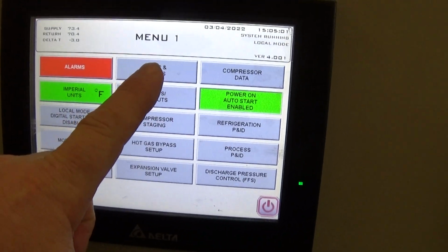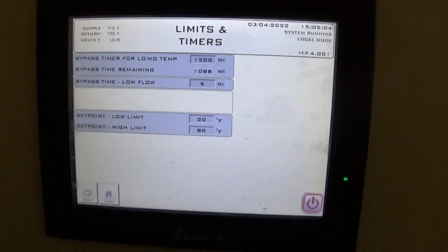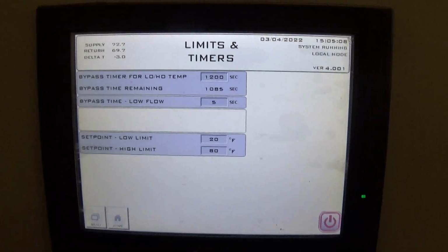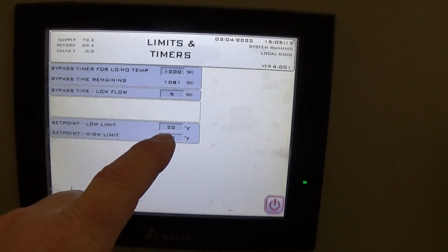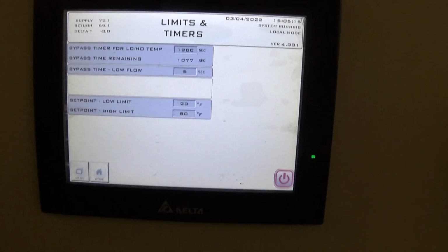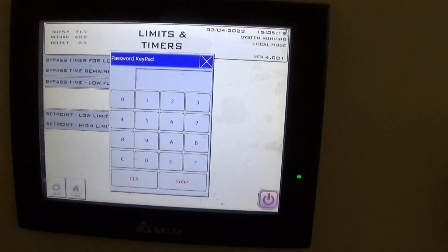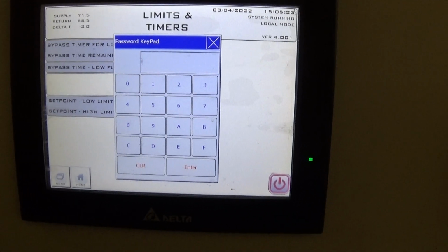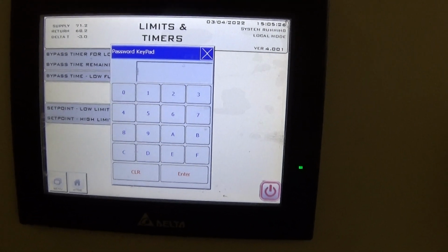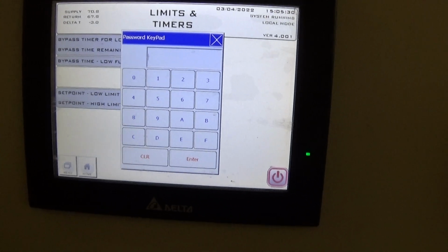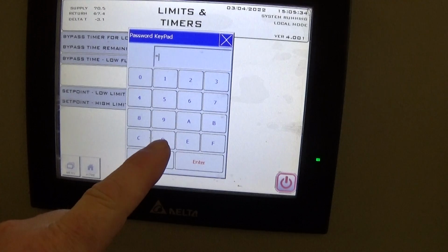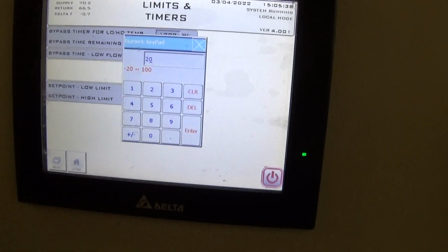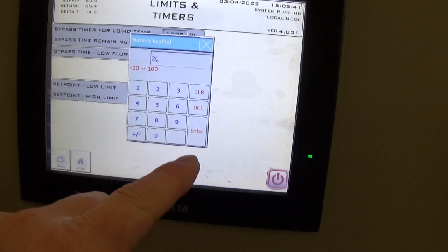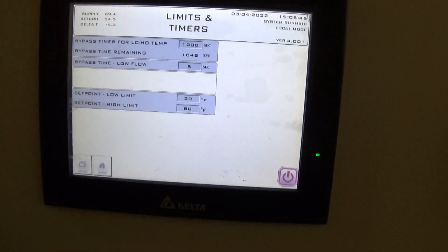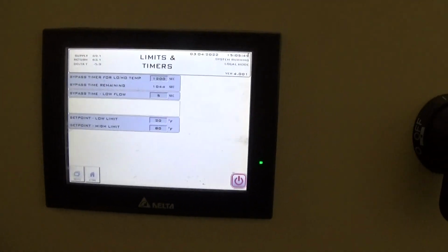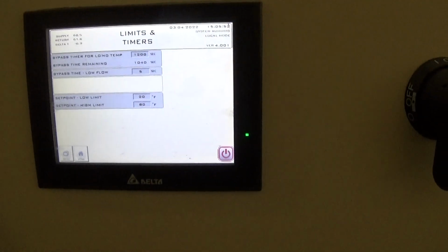Menu. Limits and timers. We got a bypass timer for low and high temperature, bypass timer for low flow. We have a low limit, lowest set point of 20, and currently a high limit of 80. We could actually change those. Just as an example, if I press that 20 there, that's probably a technician level password, which should be 1987. So you got two passwords, 9999 and 1987. 1987. Enter, and I could go in there and I can change that. But I like 20. You can hear this noise like an airplane taking off. That's basically the compressor ramping up a bit.